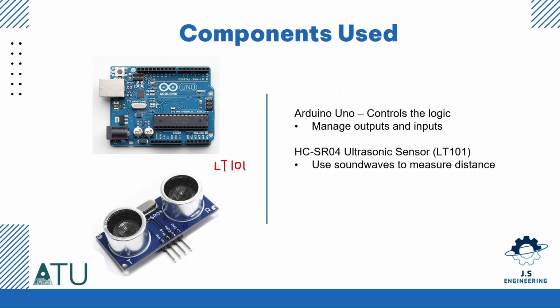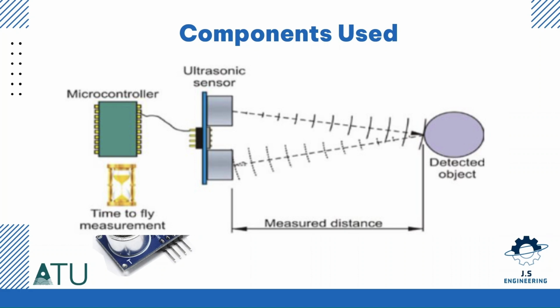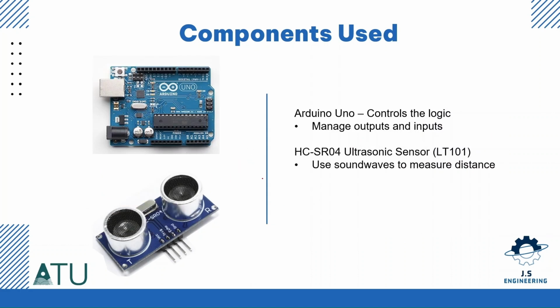It measures the tank level in TA101 using ultrasonic sound waves. So basically it sends out a sound pulse and calculates the time until the echo returns, converting that into distance. You must calibrate the sensor. Imagine you have your tank here, which is 25 liters in total. You have your ultrasonic sensor here, and the total distance will be, for example, 40 centimeters. Measure, for example, 5 liters and pour it here. And then you find the distance. 40 centimeters will be 25 liters. And when it's distance x, it will be 5 liters.